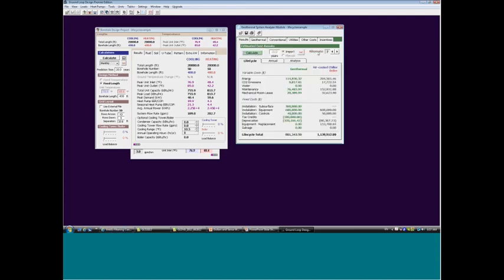When I go to my results here, I can see my simulation results for my first design and for my second design, and see the difference. With this high efficiency system, you see my energy costs are a bit lower. I'm saving about $25,000 a year in energy costs. Then over the life cycle, I'm saving about $30,000. So you can analyze different scenarios against the geothermal system, and that's the function. You can have up to 5 alternates that you compare at one time to your geothermal system. Make sense? Does that answer your question, Adam?